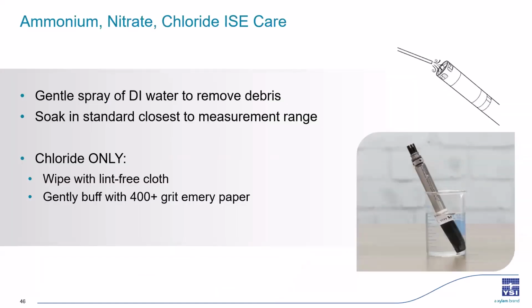To clean ammonium, nitrate, and chloride ISE, you can use a squirt bottle to spray them gently with DI water to remove the debris, and then soak the tip in its standard for at least 15 minutes. You're going to want to use the standard that's going to be closest to your expected sample measurement, so either the lower or higher concentration. For those of you who are measuring in natural water bodies, you're probably on the lower end of the sensor range. So you would just go ahead and use the lower concentration standard, which would be 10 milligrams per liter for the nitrate, for example.